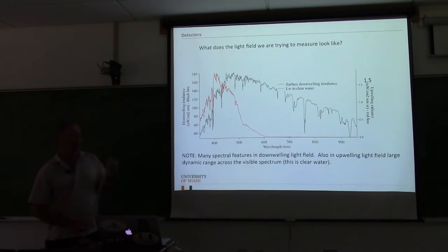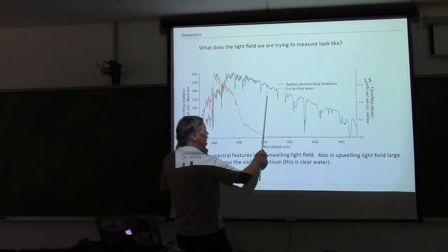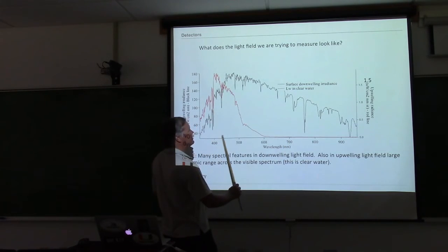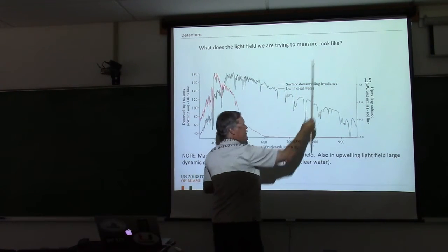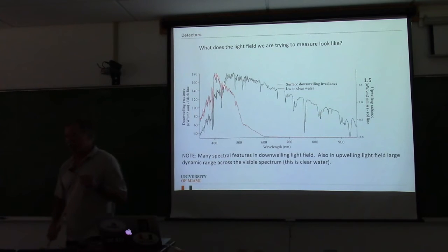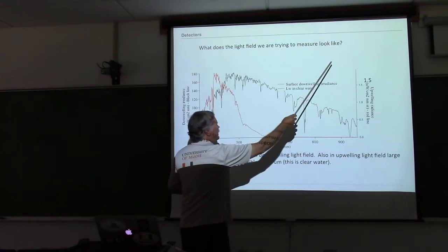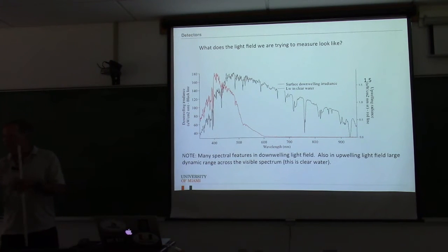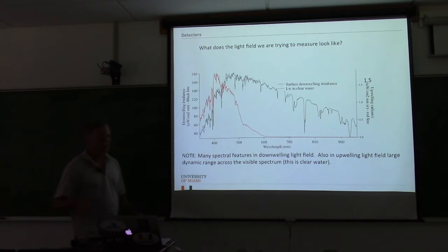So the black body curve for a lamp probably peaks somewhere up in here. It has very little blue light, and it's going up tremendously in the infrared. So when you have a calibration source that looks like that, and you try to measure this or that, you're going to get different answers. So calibrating a broadband instrument is a really difficult problem.